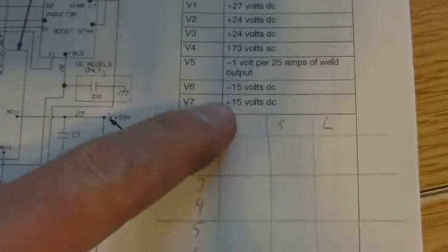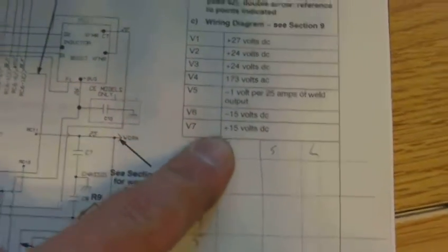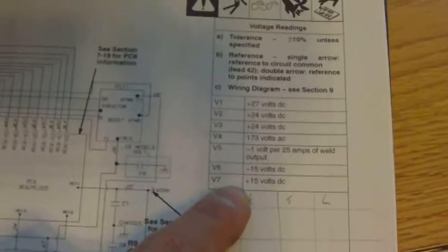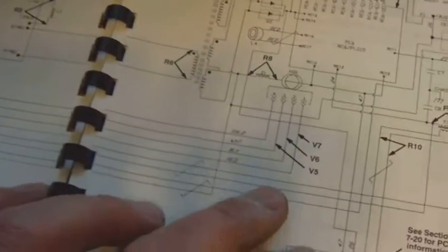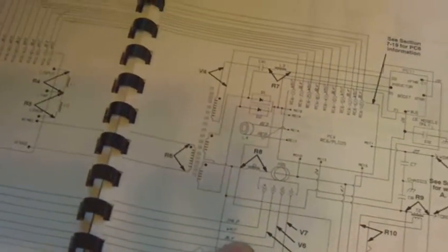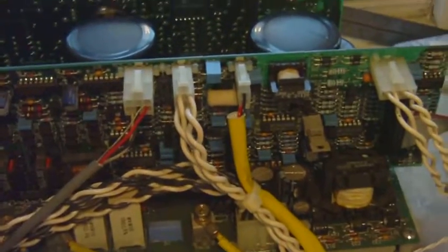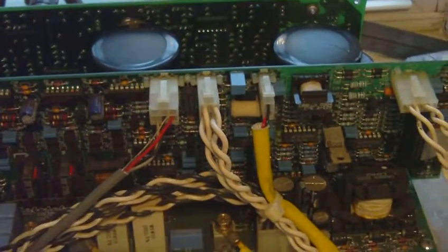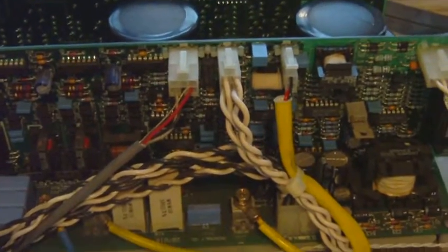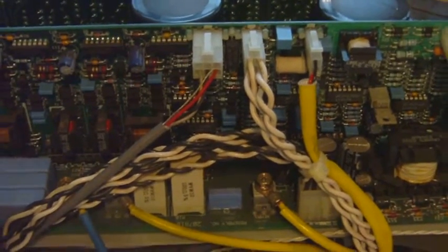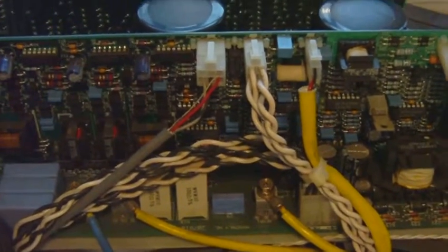And I'm supposed to see, what is it? Negative 15 volt DC and positive 15 volt DC on the red and black wires relative to ground. And again, I get nothing. So that means either the inverter controller board is bad, the power interconnect board is bad, or the power module is bad. I can't tell which.